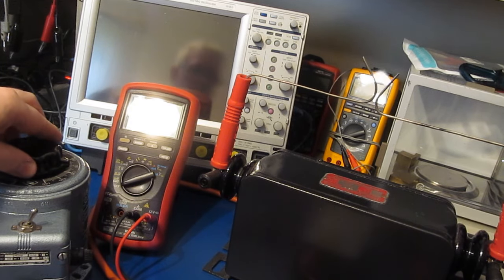What we can do is just increase our gap a little bit. Maybe we can see where the leads actually will break down at. At about 6000 volts I can hear this bundle singing. I'm going to move the camera in a little closer. Right here is 4000, here's 5000. I don't know if you can hear that, this is 6.1 kV right here. She's singing pretty good. The main gap just broke down.